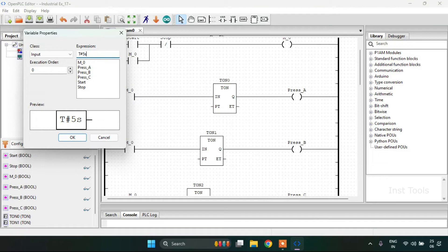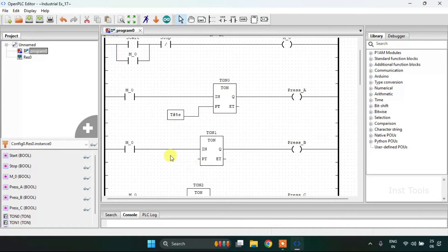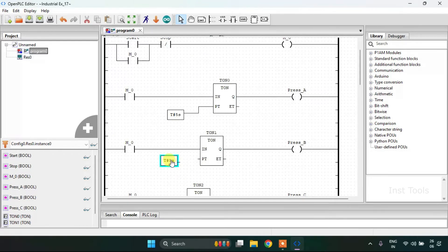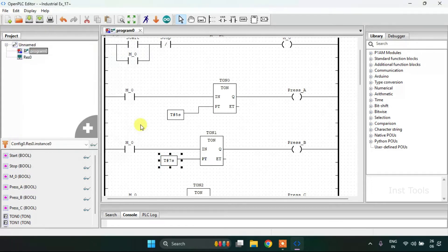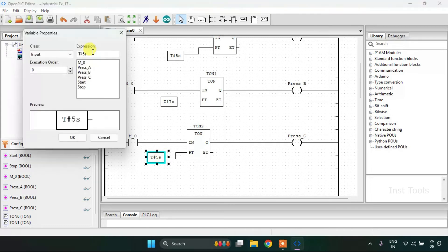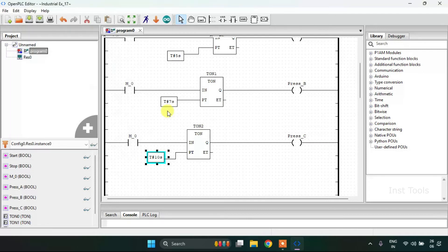And I will write T hash for my first block. The preset time is going to be five seconds. Then I'm going to copy and paste the same variable for my second block and join the pin. Then double click on the block and change the preset time. And do the same for my last block. Double click on the variable and change the preset time to 10 seconds.